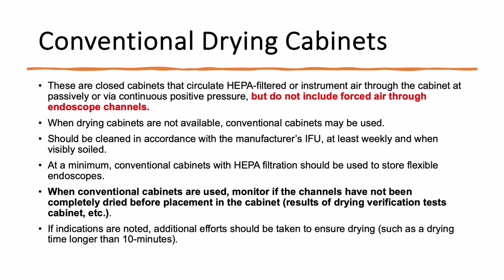They have to be cleaned according to the instructions. These cabinets with HEPA filtration should be used to store flexible endoscopes at a minimum. If you don't have at least HEPA-filtered air in your cabinet, you need to get one. When conventional cabinets are used, monitor whether the channels have been completely dried before placing them in the cabinet, so you should use drying verification tests, because remember, your conventional cabinet does not dry the internal channels. If there are indications that the scope is still wet, additional effort should be taken to ensure drying, and that could include more than 10 minutes of drying of each channel.